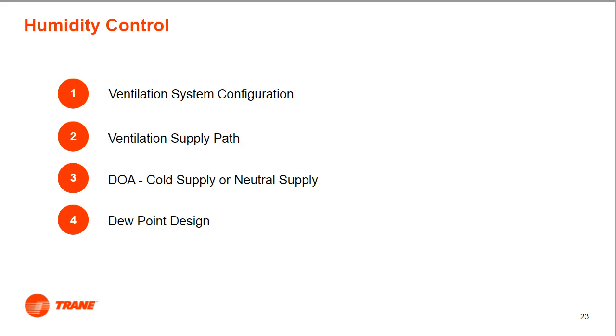How exactly does outdoor air affect the humidity design of your commercial space, and how can this be addressed with a complete VRF system design? As you see here, there are 4 main considerations when determining how humidity should be addressed. The first being, how should the ventilation system be configured for humidity-related concerns? Next, how do we determine the supply path for the ventilation system? Then, at what temperature should the outside air be provided to the space? And finally, what role does the dew point design play when introducing outside air into the space?